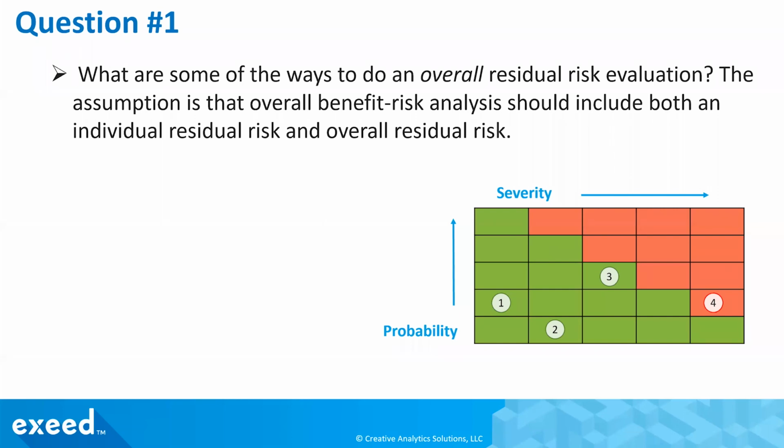You will do that for everything. And one best practice I can share with you is to map it out like this. You are supposed to do severity and probability assignment for each individual risk. You could map it out in a simple illustration to show where everything is, right? So that's individual. And of course, you also have to do overall residual risk. And we'll talk a lot more about that in our conversation, how to do that.